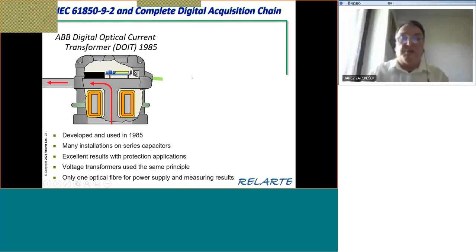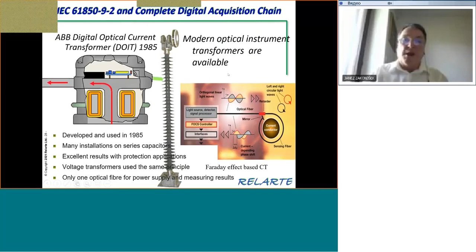Today, as we said, we are using Faraday effect-based current transformers, which look into the phase difference between incoming and outgoing light. Light comes in around the current conductor, comes back from the mirror, goes back, and here we are doing signal processing and so on. This is called, among other things, a low power instrument transformer or optical instrument transformer.